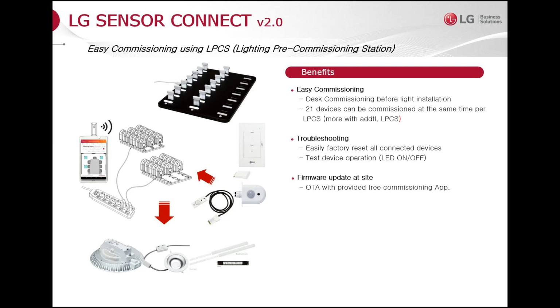When you've commissioned it, the commissioning program is saved inside the flash memory of the dongle or sensor. That means you can disconnect them, put them in a box or bag, label them, for example this is Office 1, this is Conference Room 1, and hand them to the installers. When they go to plug them in, there's no further programming needed.